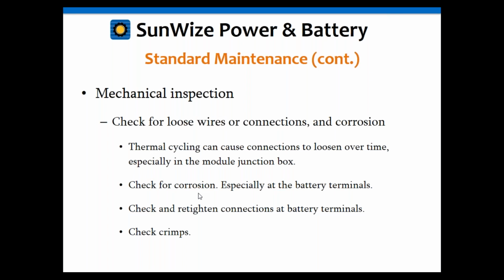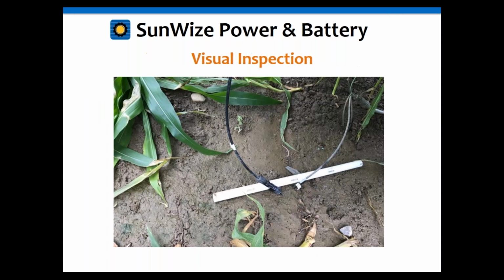Also check those for tightness. Those are also ones that loosen quite a bit, again because of thermal cycling with the batteries and just the fact it's hard to get a tight connection on those, so always check those as well. And crimps, that's another one. If you have crimps on your battery terminals or on other terminals with compression lugs like that, you just want to double check that there are no loose connections there as well. Same thing going on. You can have looseness over time. So just something else to check with your mechanical inspection.